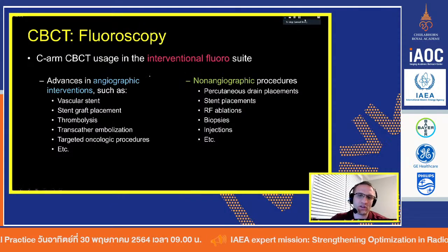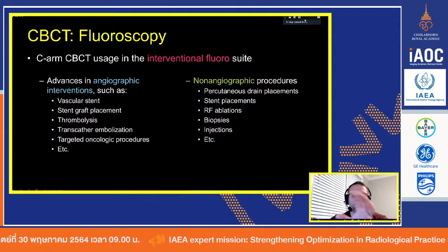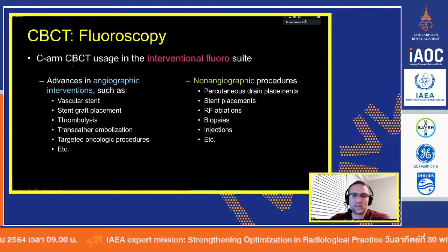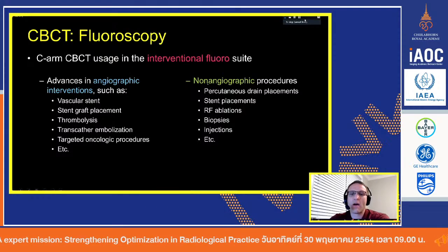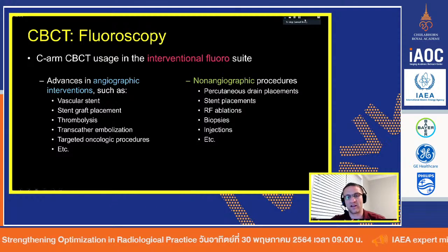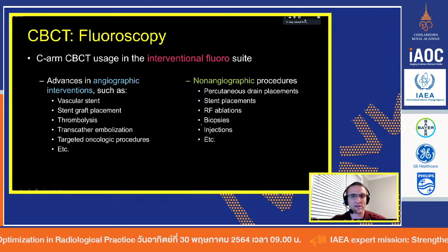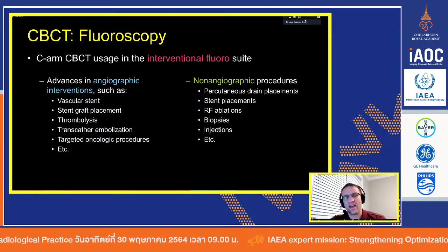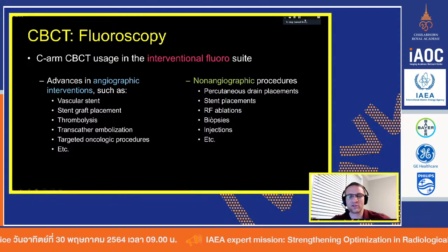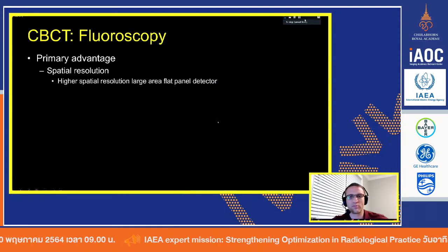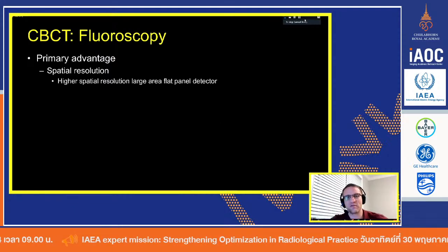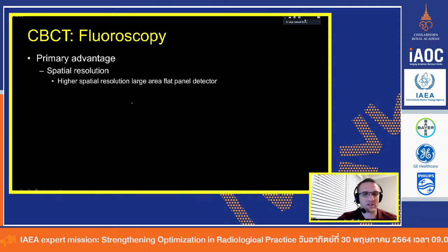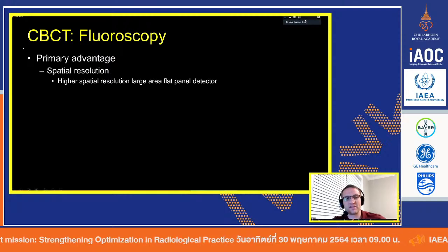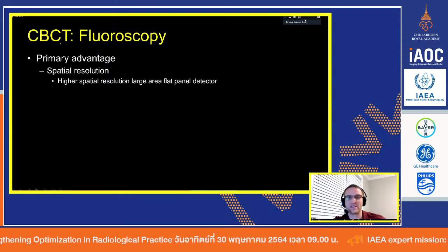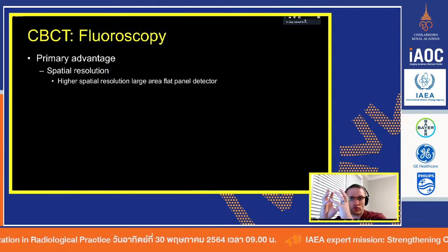So obviously, what are the uses? You could largely group these two: the use of CBCT in IR in angiographic and non-angiographic procedures. My personal experience is on the non-angiographic, where we do a lot of biopsies in our pediatric hospital. And so I would say I've worked the closest with our IR docs trying to set up good dose reduction and imaging practices for our cone beam CT acquisitions. What are the primary advantages of using CBCT over traditional CT scanners? So C-arm versus traditional CT.